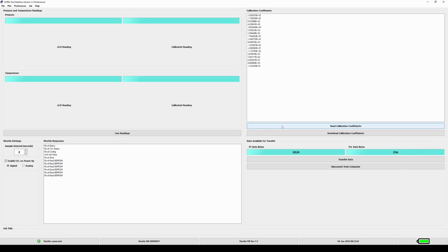Once we come into the back end homepage, we'll see this is where the calibration coefficients are stored, along with a number of other things used for repairing and updating the software. What you really need to focus on is the live readings button. This will pull up the temperature and pressure reading while the shuttle is plugged into your computer.